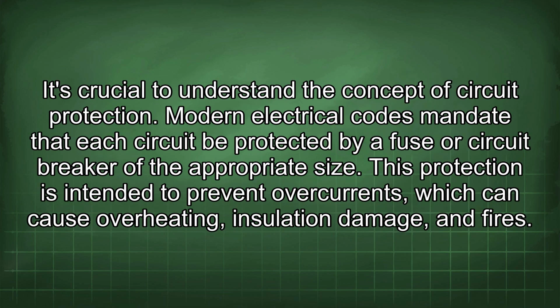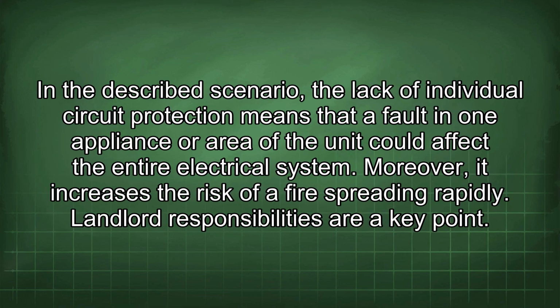It's crucial to understand the concept of circuit protection. Modern electrical codes mandate that each circuit be protected by a fuse or circuit breaker of the appropriate size. This protection is intended to prevent overcurrents, which can cause overheating, insulation damage, and fires. In the described scenario, the lack of individual circuit protection means that a fault in one appliance or area of the unit could affect the entire electrical system. Moreover, it increases the risk of a fire spreading rapidly.